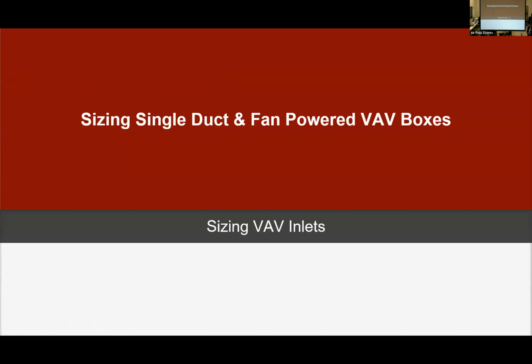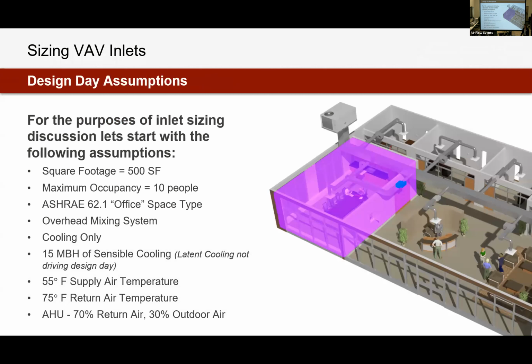All right, so now we're going to look at how we actually size single duct inlets to achieve what we ultimately want in the field. This is usually a job of the engineer when they're setting up plans. They're going to be the ones to determine how much airflow we need in the space and then ultimately determine what size of equipment we need. We're going to go through an example here. So we're looking back at that office building, but we're going to focus on this one room. We're going to call this a multi-purpose conference room, and that will eventually get us to the final airflows that we need.